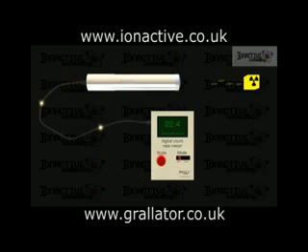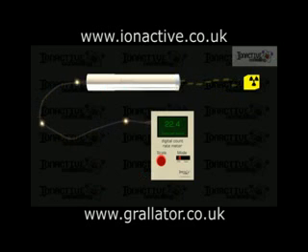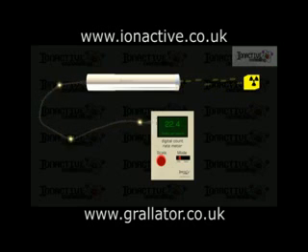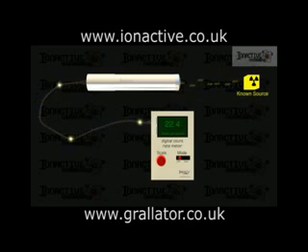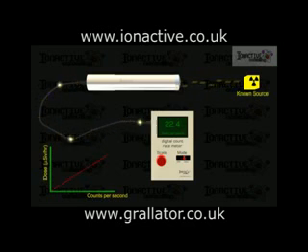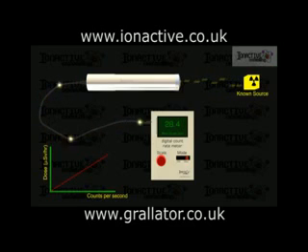The raw output from a GM tube shows a fraction of the radiation counts per second, which is modified by taking account of the dead time to give the actual counts per second. If the radiation type and energy are known, then the counts per second reading may be calibrated so that the unit gives an equivalent dose rate.